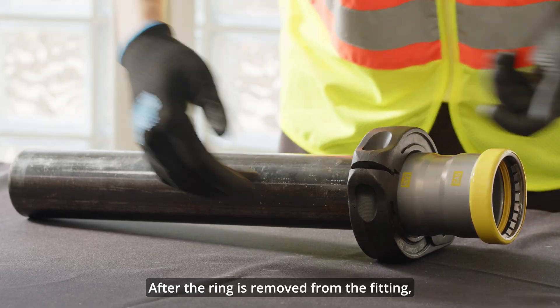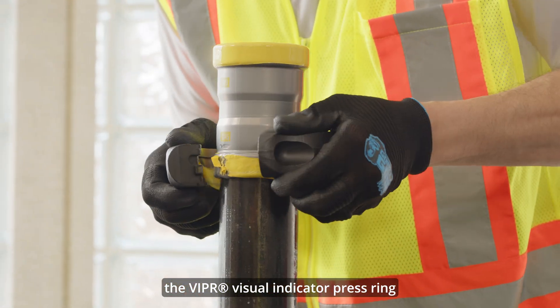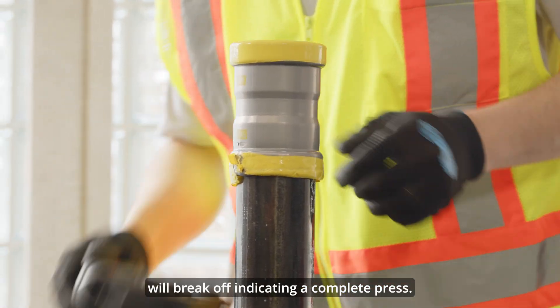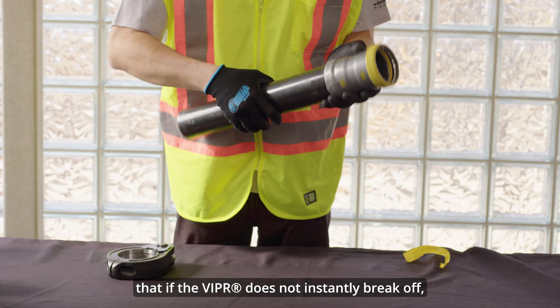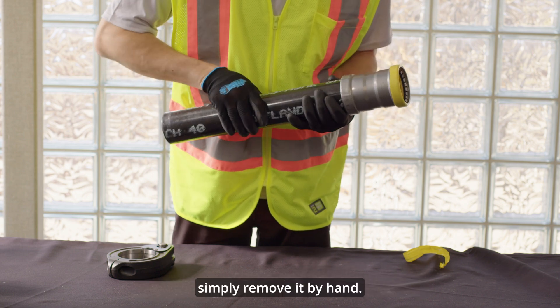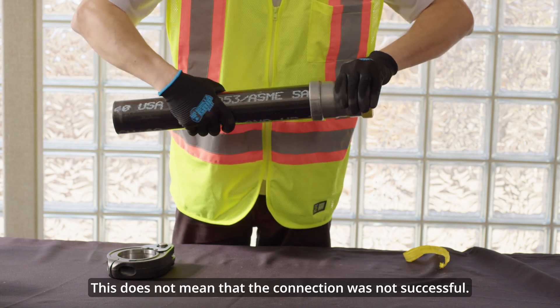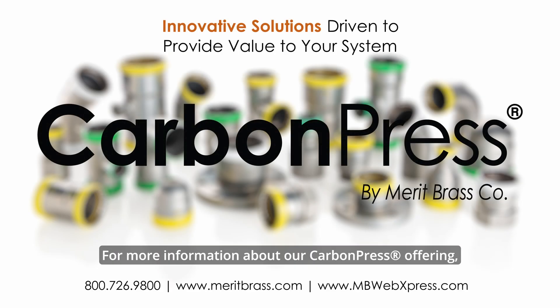After the ring is removed from the fitting, the VIPR visual indicator press ring will break off, indicating a complete press. It is important to note that if the VIPR does not instantly break off, simply remove it by hand — this does not mean that the connection was not successful. For more information about our CarbonPress offering, please visit our website or contact our team today.